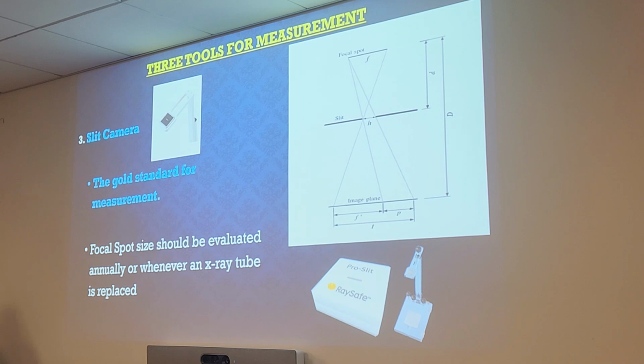The camera is used to measure the focal spot size. So it's on, they keep it on the base. You see the base here. This is the slit camera itself. This is what it looks like up close. Basically what you do is you set this base on the table, or you'll set your IR on the table. Set the base next to the IR on the table, you can extend this piece here, because it does move.